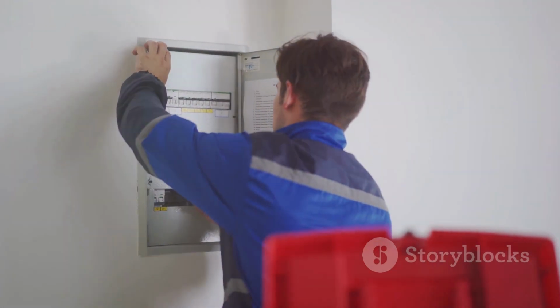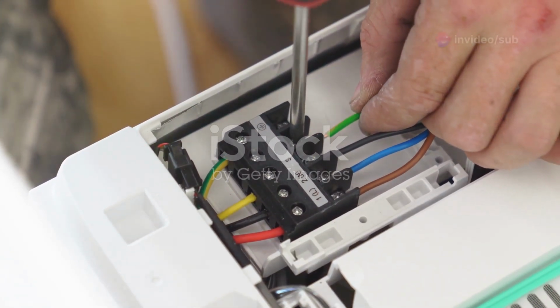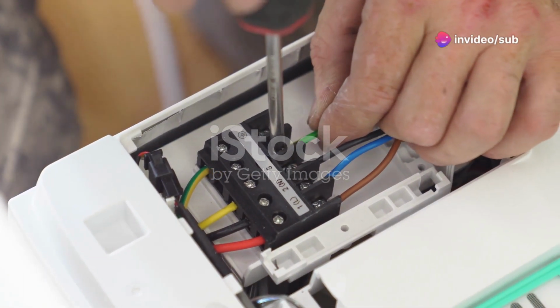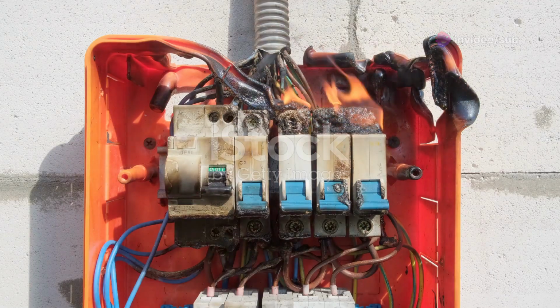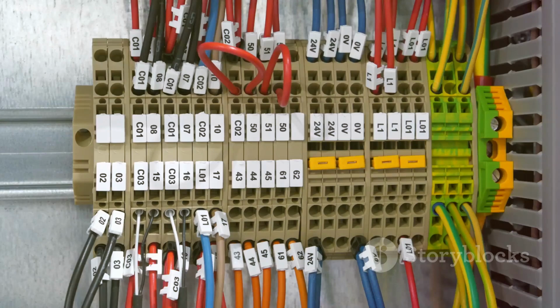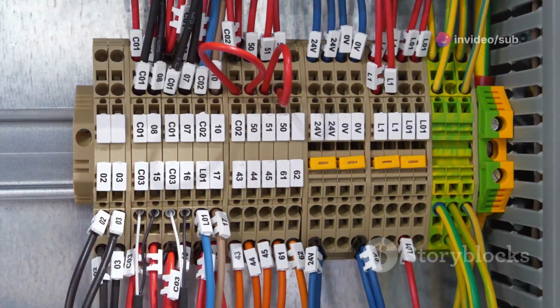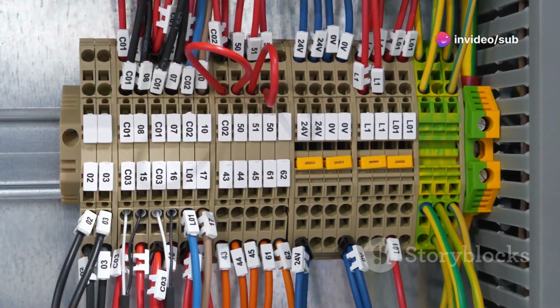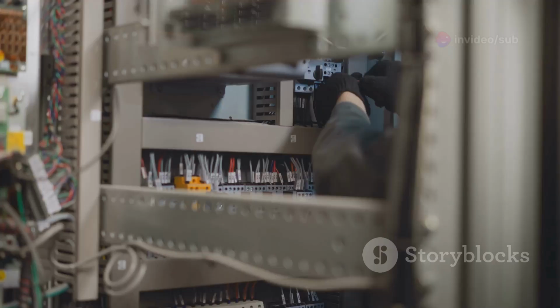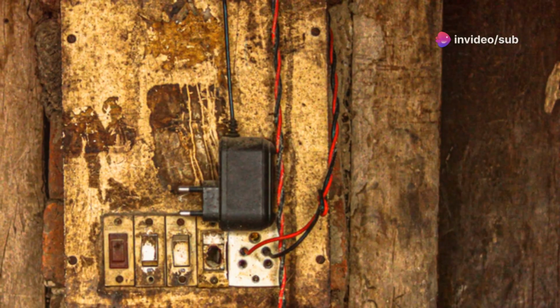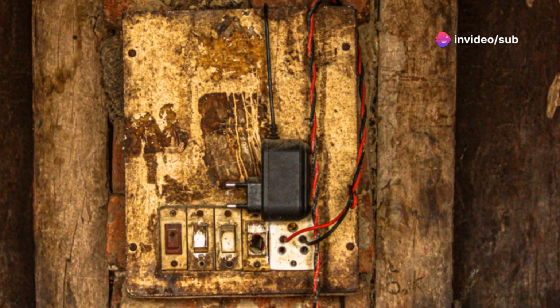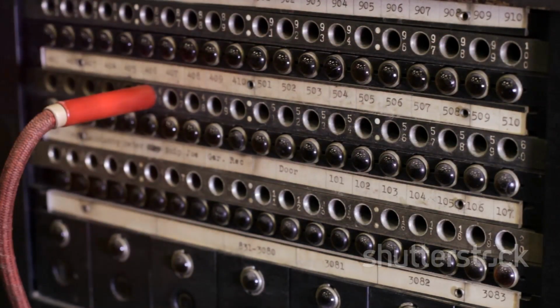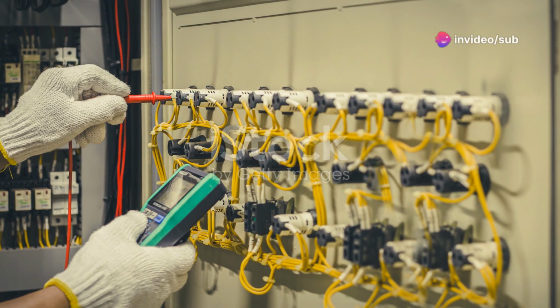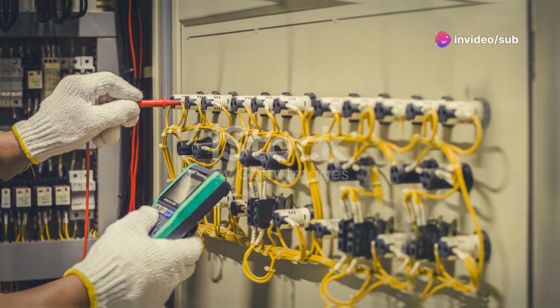Even with a well-designed breaker, wiring mistakes can happen. One common mistake is stuffing two or more wires into a single terminal when the breaker only allows one wire per terminal. This can lead to loose connections and overheating. Another mistake is mixing different wire sizes in the same terminal. Thick and thin wires don't clamp evenly, which means one wire could slip out or make a poor connection. That can cause dangerous arcing or even fires. People also forget to tighten terminal screws to the correct torque. Too loose and wires can wiggle free. Too tight and you risk damaging the wire or the breaker terminal. Some even confuse the line and load sides, wiring them backwards, which can cause equipment to malfunction. All these mistakes are preventable. A few extra minutes spent double-checking your work can make a big difference in safety.